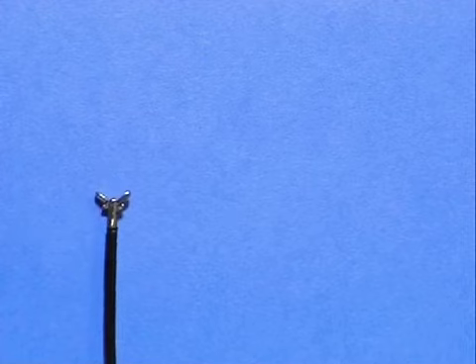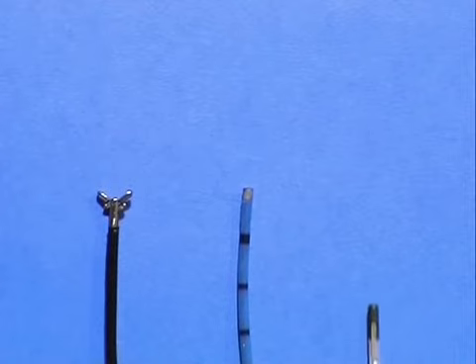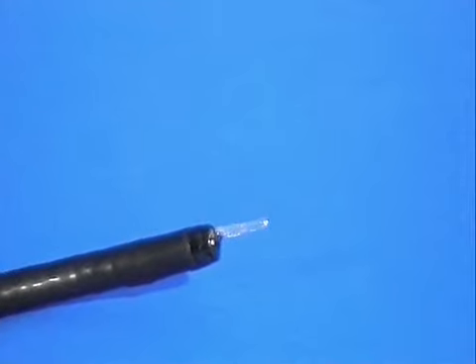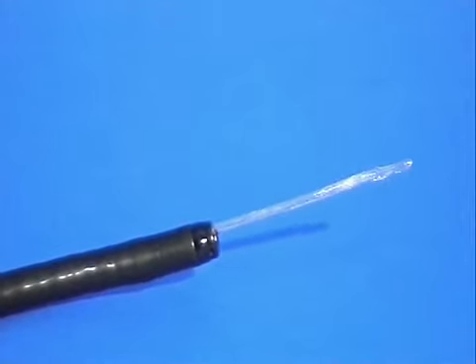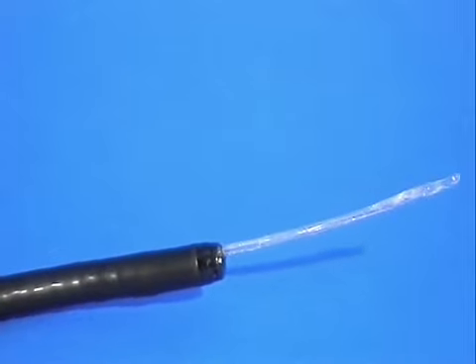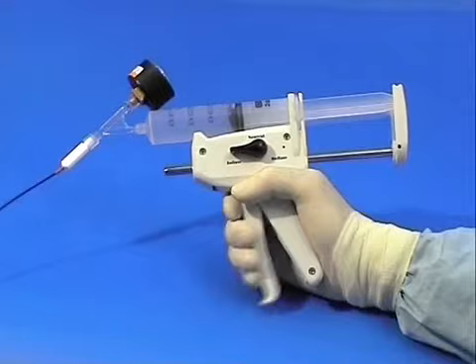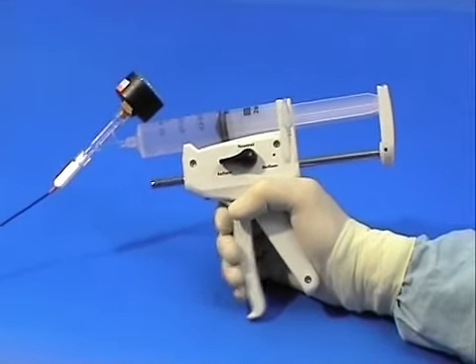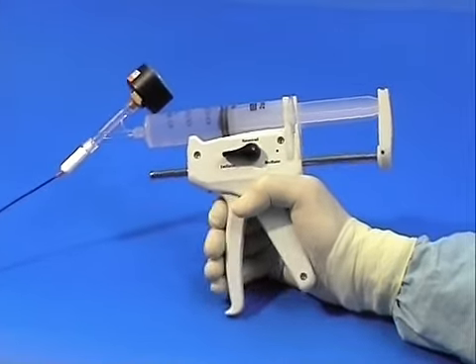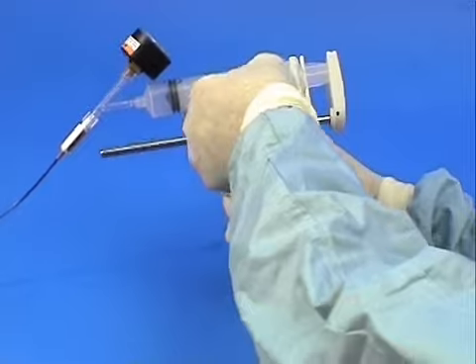Coagulation devices are also essentials, whether hot biopsy forceps, plastic insulated, the argon plasma coagulator catheter, or the heater probe, Teflon covered. The best stricture dilating balloons are the guide wire variety. They furl up tight enough to pass through a small scope channel, and the guide wire makes passage through the stricture easier and safer. 15 and 18 mm balloons should be ideal. A pressure gun like this is essential to reach the high distension pressure needed, and it can be switched into reverse to deflate the balloon again.